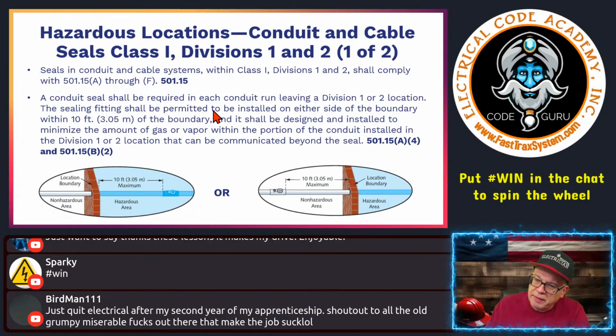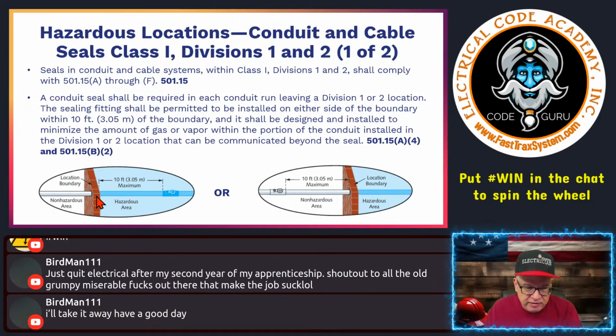The seal fitting shall be permitted to be installed on either side of the boundary within 10 feet. Ding, ding, ding, exam type question, right? Of the boundary. And it shall be designed and installed to minimize the amount of gas or vapor within the portion of the conduit installed in the Division 1 or Division 2 location that can be communicated beyond that seal. So if you look at this example here, here's your boundary. So this is your area. So they decided they wanted to install the seal on the hazard side. As long as it's within, okay, here, within 10 feet, then the seal could be on the inside.